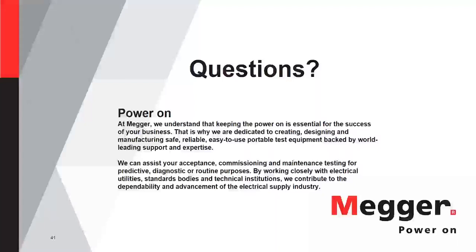During the commissioning of a new substation battery bank with 495 amp hours and 59 cells, the first capacity test was interrupted due to testing equipment tripping. A second capacity test is to be performed. Do we need to equalize the battery bank again before doing the capacity test? On this one, you would first have to fully charge the battery back up, and then you want to equalize it once again, and the standard requires you to do it 72 hours before performing the testing. I'll even mention on this one, Clay, because you want to give every cell an equal starting point. Some cells might have pulled down a little bit more than the others, so you'd rather equalize them all again.